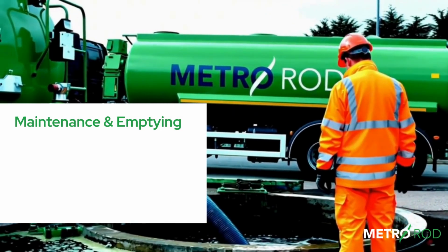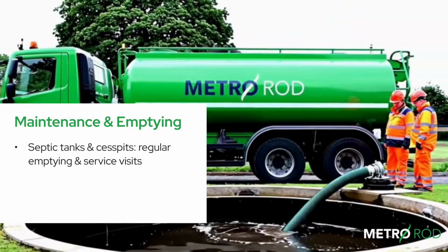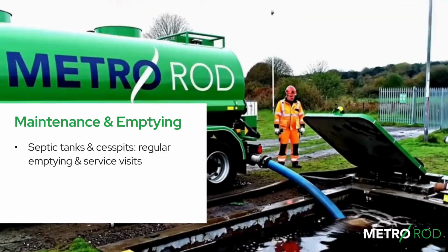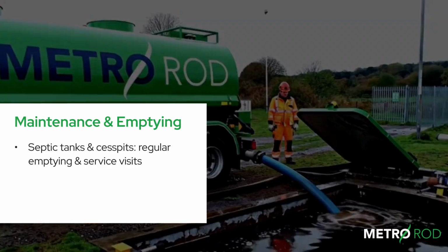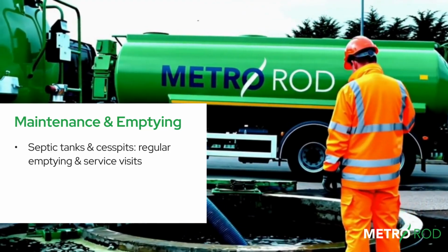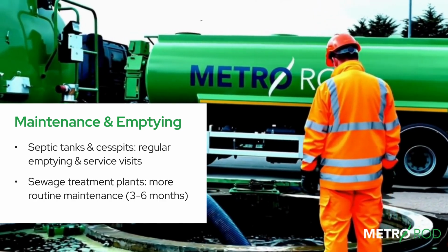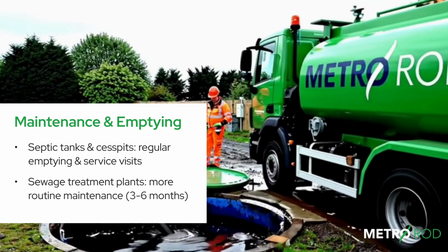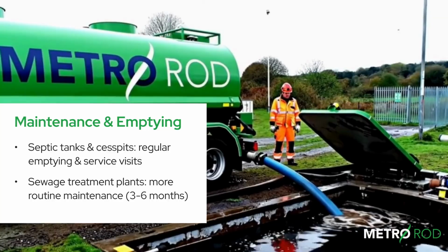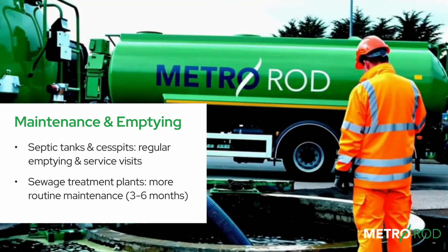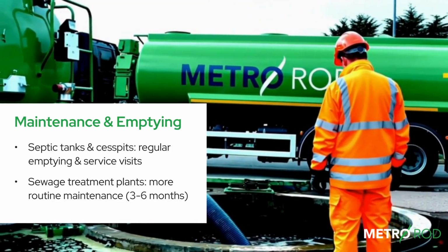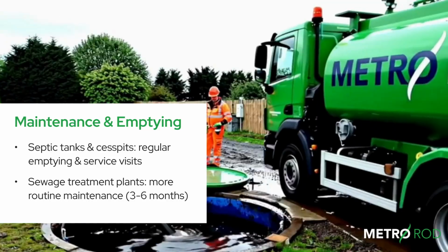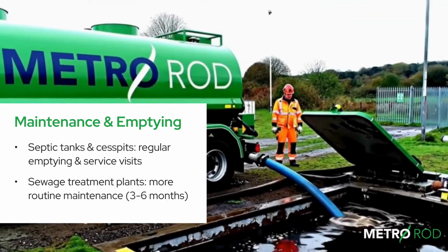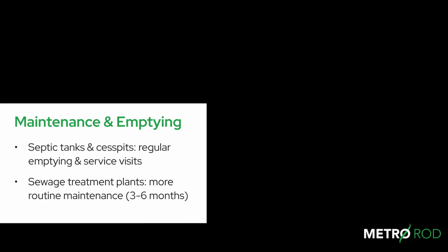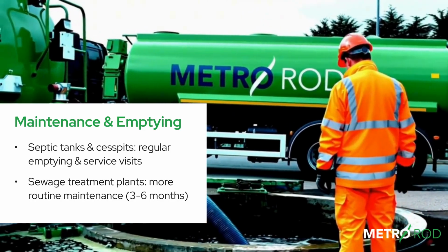All three systems require maintenance. Septic tanks and cesspits should be emptied at regular intervals, removing sludge and scum to prevent blockages and prolong tank life. Sewage treatment plants need more routine maintenance and service visits than septic tanks, typically every 3 to 6 months. While septic tanks are emptied more often, treatment plants are more susceptible to wear and tear due to their additional parts, like air pumps and filters.